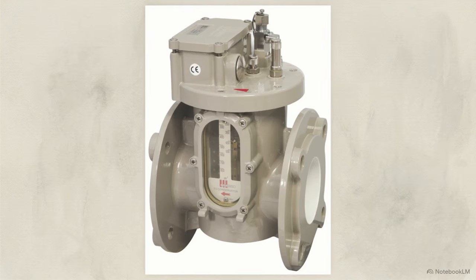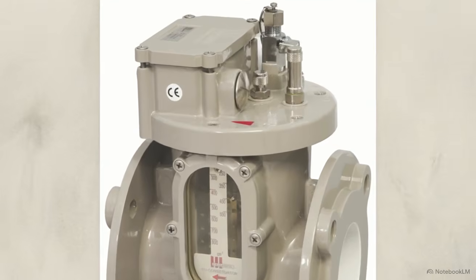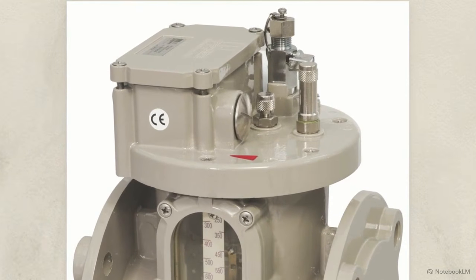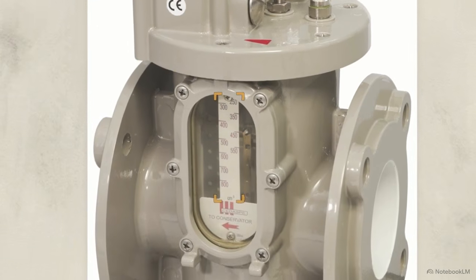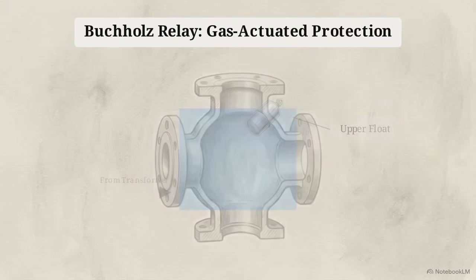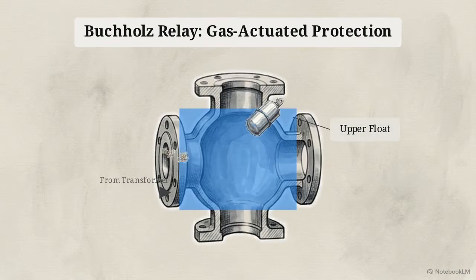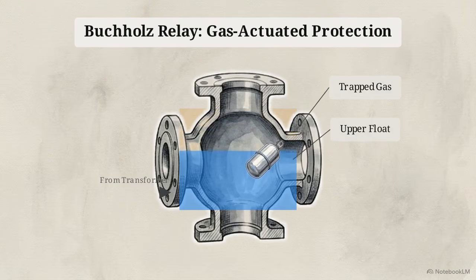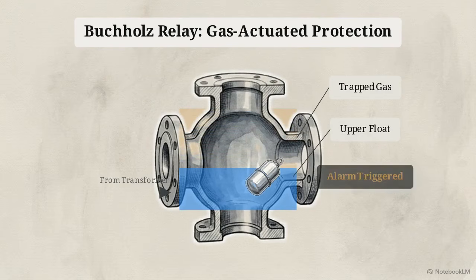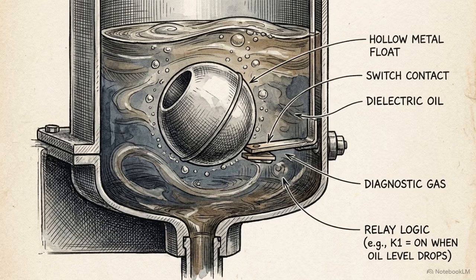Engineers install a Buchholz relay, a mechanical gas trap in the upward piping. For minor faults, the generated gas slowly rises and accumulates at the top of the housing, displacing the oil. You can see the fluid level dropping against the graduated scale. Inside the chamber sits an upper float mechanism. As the trapped gas displaces the oil, the fluid level drops, and gravity physically pulls this upper float downward. When the float descends far enough, it closes a magnetic switch.